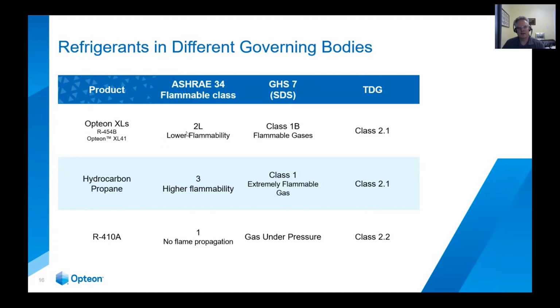You'll see that under ASHRAE 34, they're called 2L. So this is what you would see in the building codes like CSA B52, ASHRAE Standard 15. GHS, so this is what you see on the SDS sheets, which would be used for handling or storage of refrigerants.